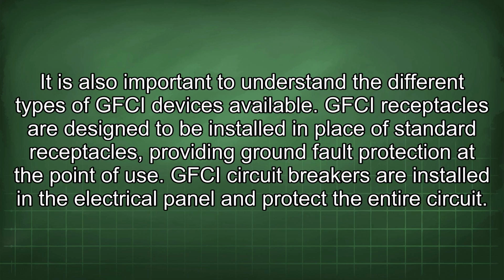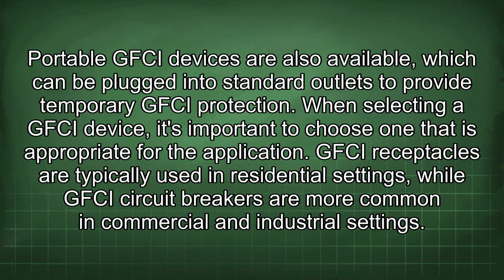It is also important to understand the different types of GFCI devices available. GFCI receptacles are designed to be installed in place of standard receptacles, providing ground fault protection at the point of use. GFCI circuit breakers are installed in the electrical panel and protect the entire circuit. Portable GFCI devices are also available, which can be plugged into standard outlets to provide temporary GFCI protection.